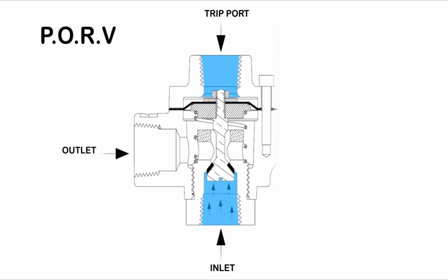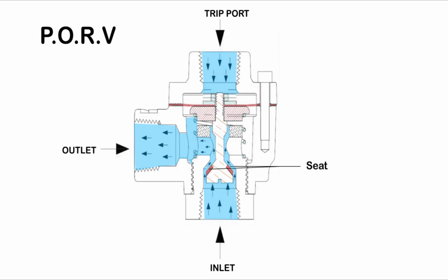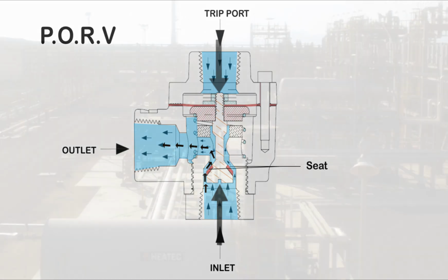In the shown figure, the valve is in closed position, where there is water pressure on the valve inlet, forcing the seat to seal between the inlet and the outlet to the drain. In case the deluge system is activated, water pressure comes from the top to overcome the water pressure present in the inlet, forcing the seat to move downwards to open the path between the inlet and the drain outlet, allowing the priming water pressure to be drained during the deluge valve operation.